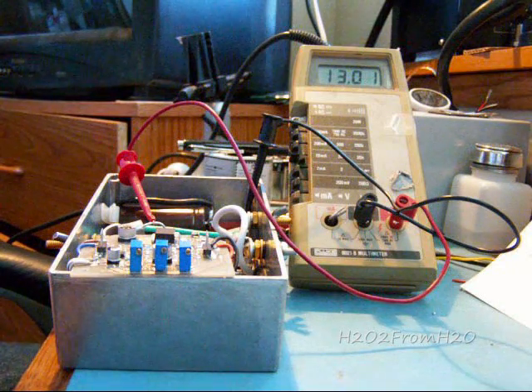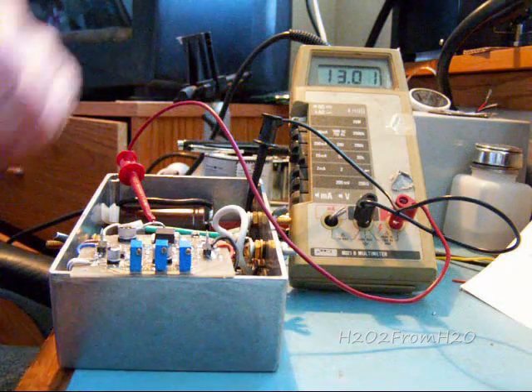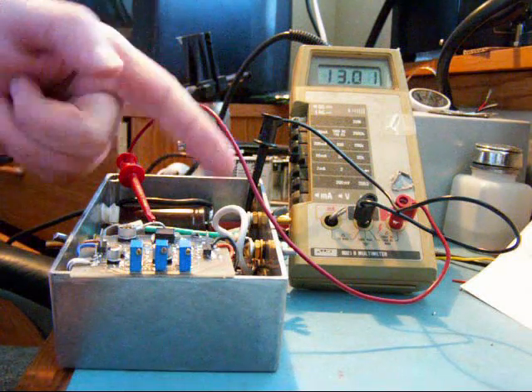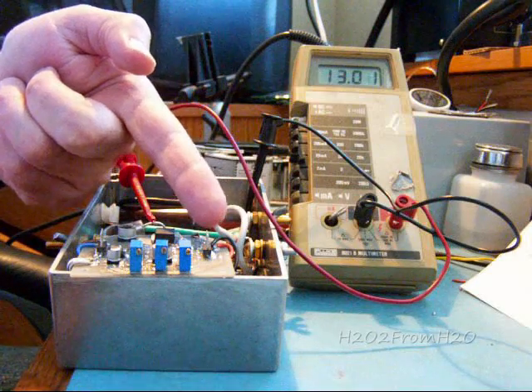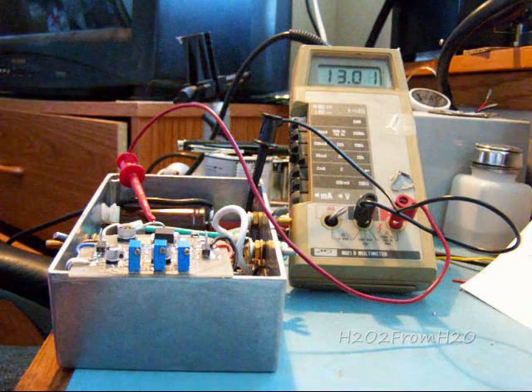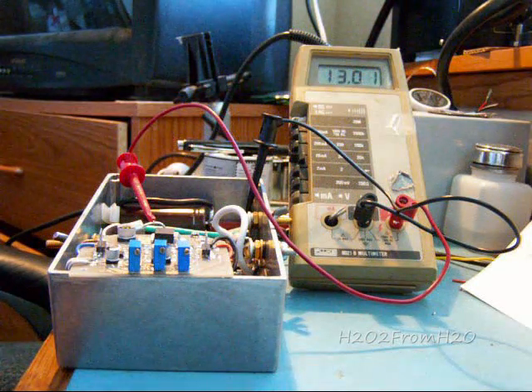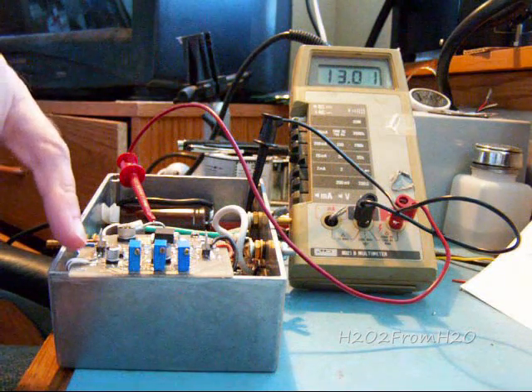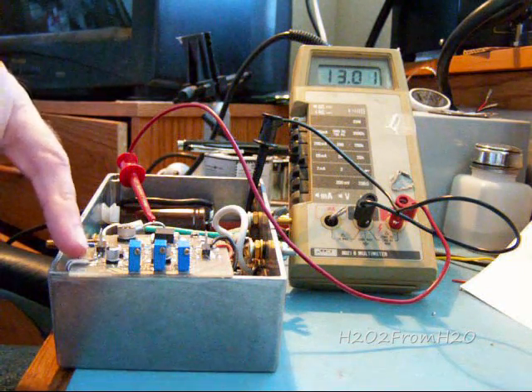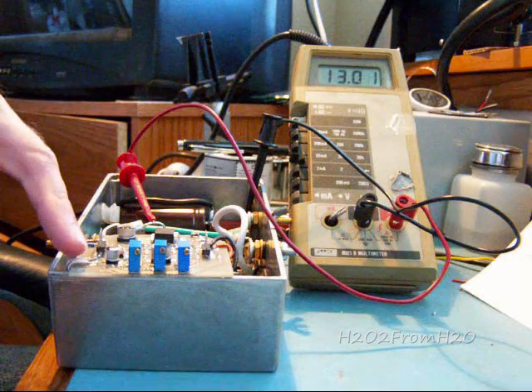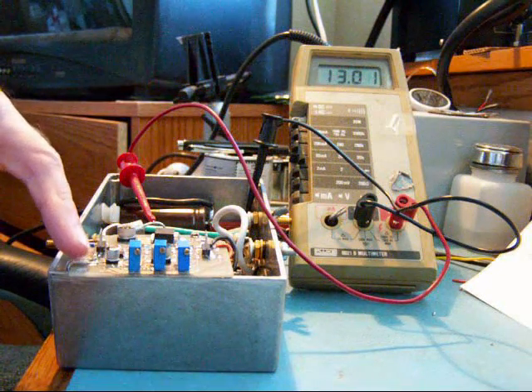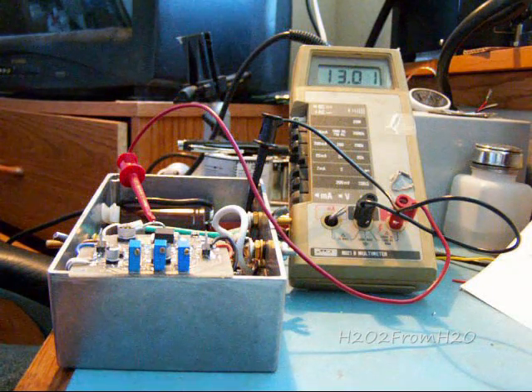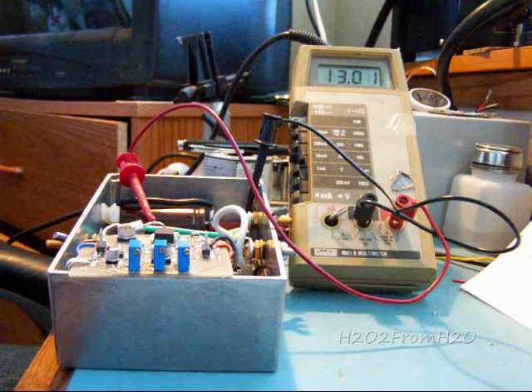If you're going to hook it directly up to a board without a case, you're just going to do a board calibration. Of course you want to hook your positive and negative leads up according to the drawing. You also have to make one other adjustment and that is that S plus and S minus. There won't be any wire there so you'll need to put a temporary jumper or shorted wire between S plus and S minus. And of course that needs to be removed after the test procedure.